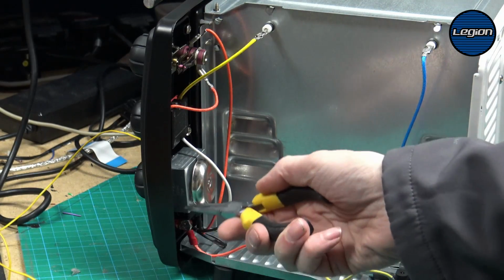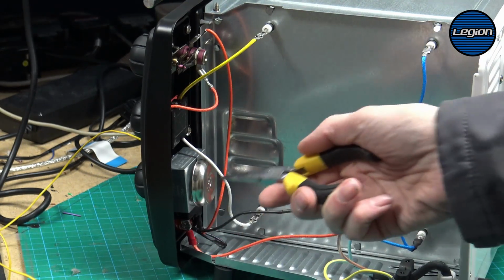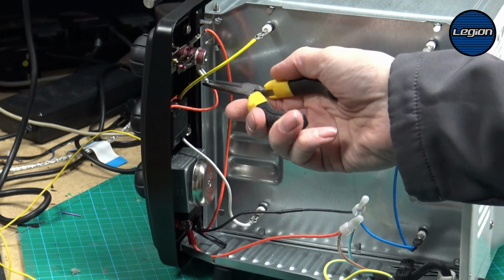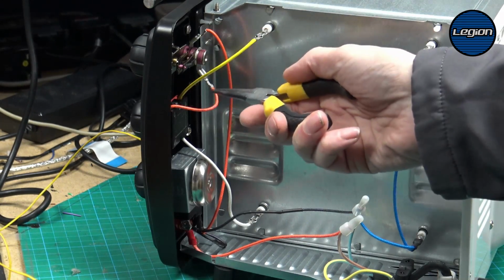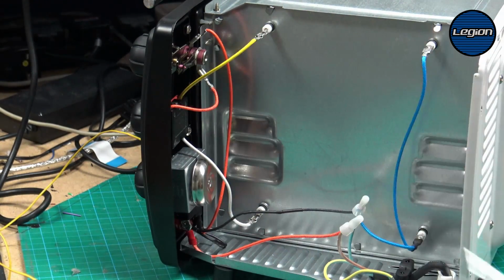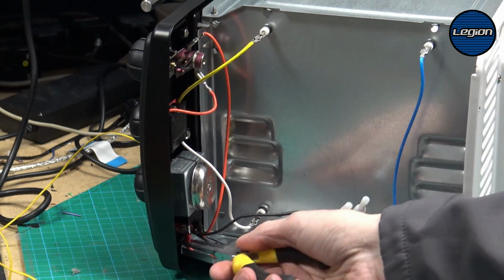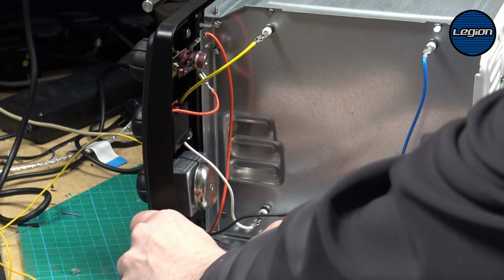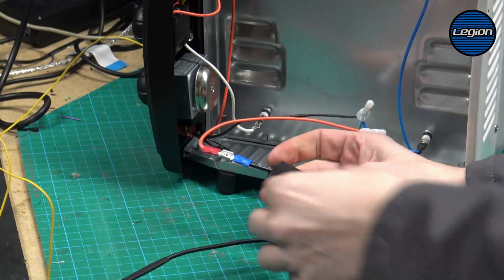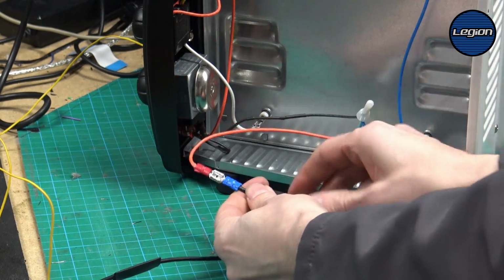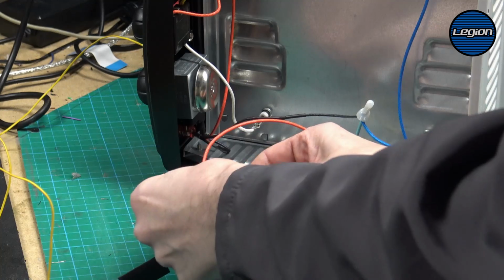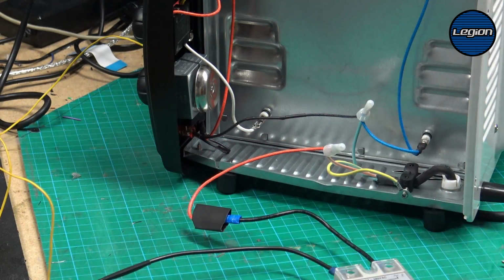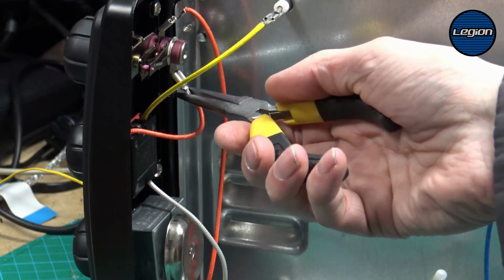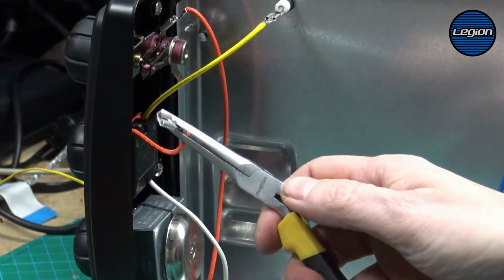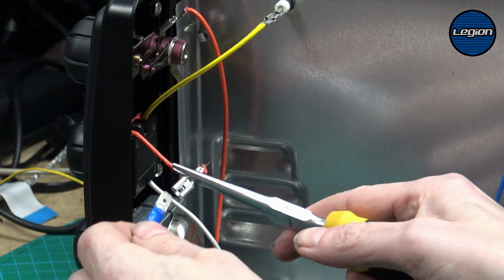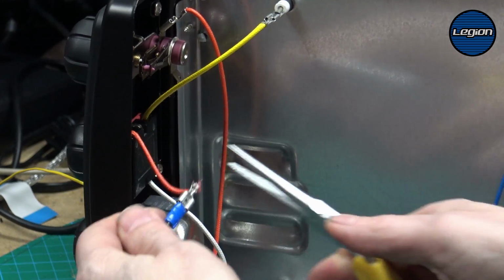The power comes in to the timer. And then we want to take this one off, which is the output from the thermostat. That just pushes on between the incoming mains and the solid state relay. Then we want to take this one off and connect that to the output of the solid state relay.